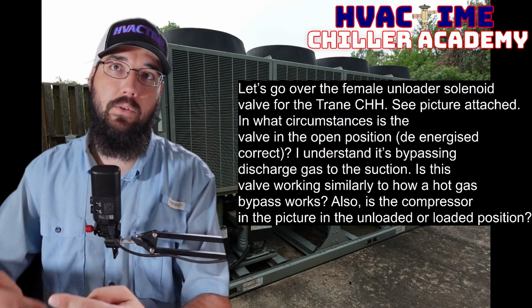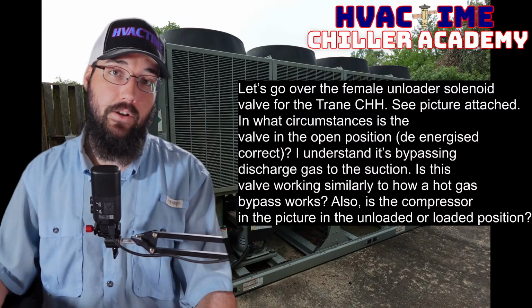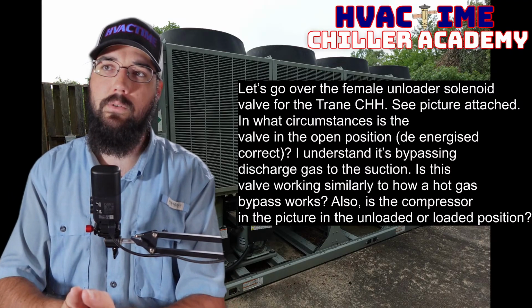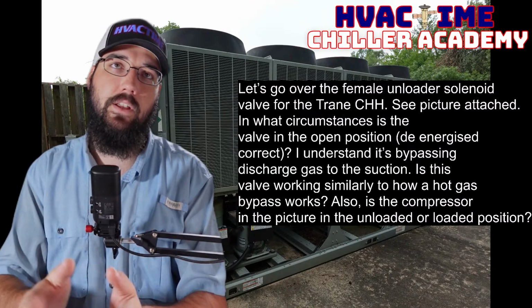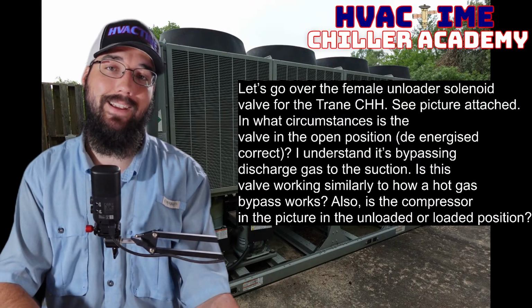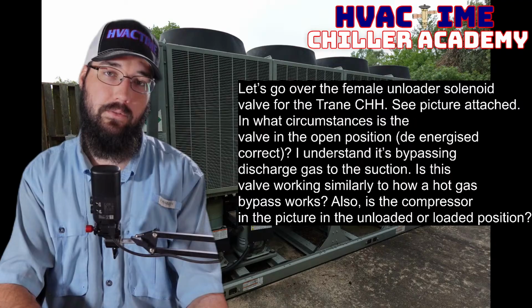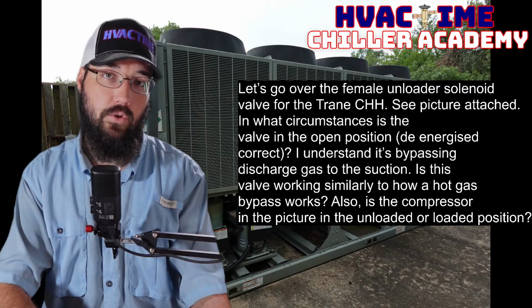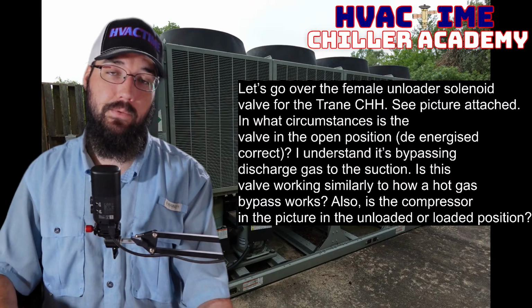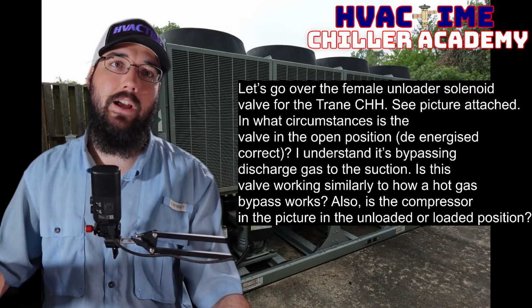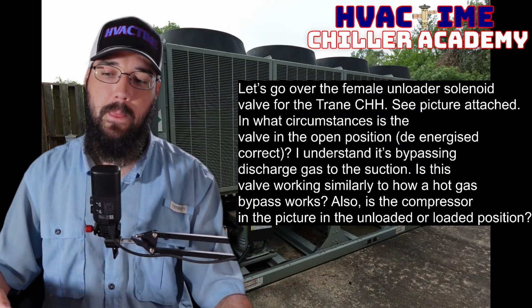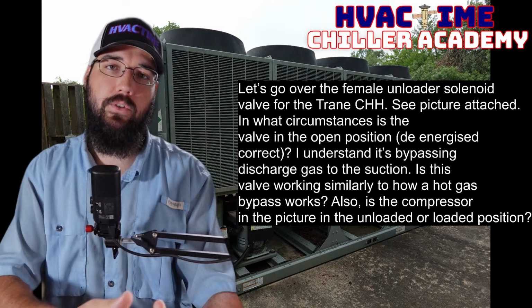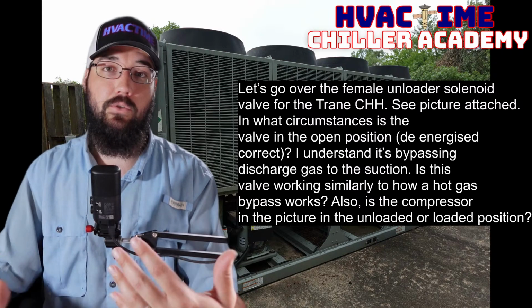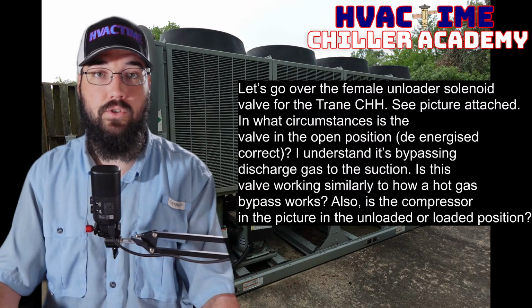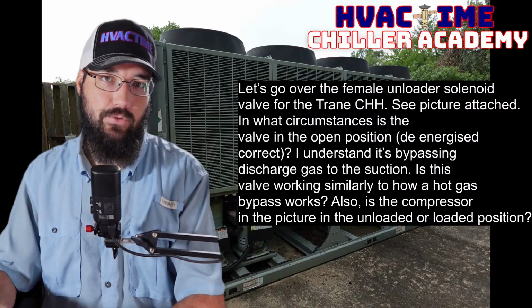So that'll be one way that you can get around that. Now, another symptom would be they stick, instead of sticking in an engaged position where the bypass is closed, they could also stick in an open position, and in that case, you're not able to actually build load on the compressor. So you need the compressor to stage up and to begin pumping more refrigerant and just do its job, and it's not able to do that.